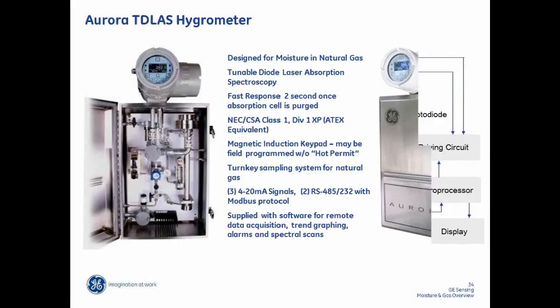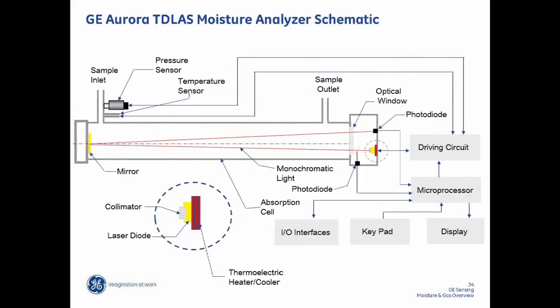The principle behind this is that we have a stainless steel tube, essentially, and inside that stainless steel, it's actually polished stainless steel, so it's a very smooth surface. And hermetically sealed away from that is a laser emitting unit, a diode laser, and there's an optical window made out of quartz. So the laser beam is shot down to a mirror. The mirror is gold-plated, and then on top of the gold is a silicon coating, which is essentially like glass. And that mirror is only used to double the path length.